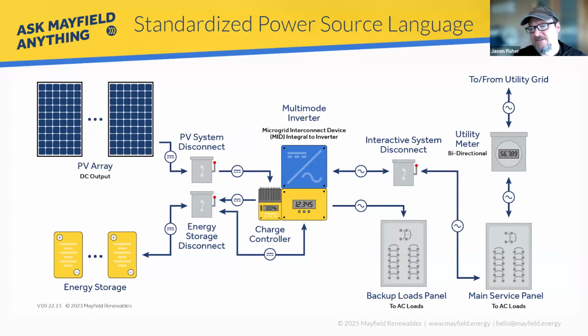That's the answer to something like, does the inverter circuit breaker qualify? The first thing you have to do is check whether it meets the requirements of 706.15 and the related 705.20. That's the first place to start, because if it doesn't, you have your answer there. It doesn't matter where it's located or what it's connected to.